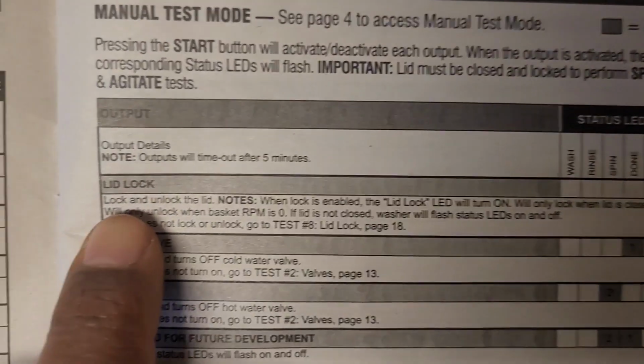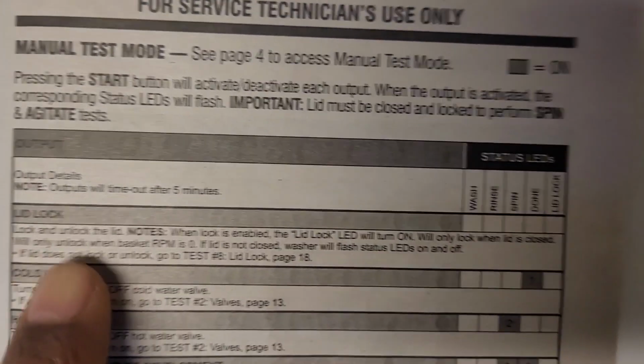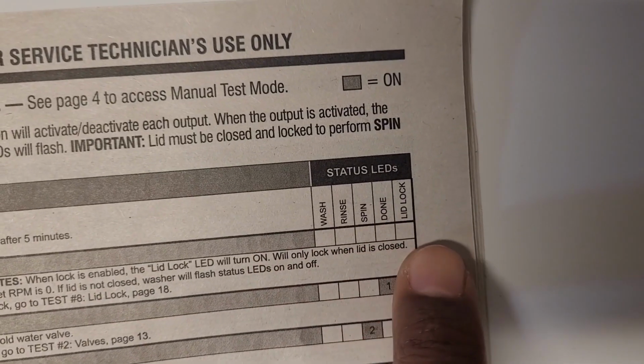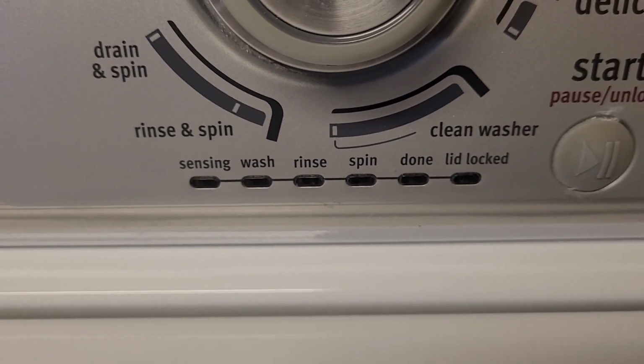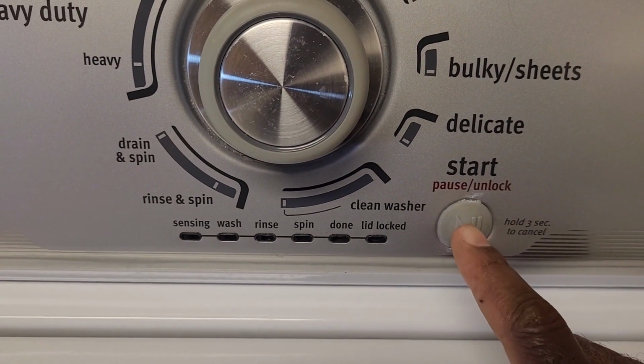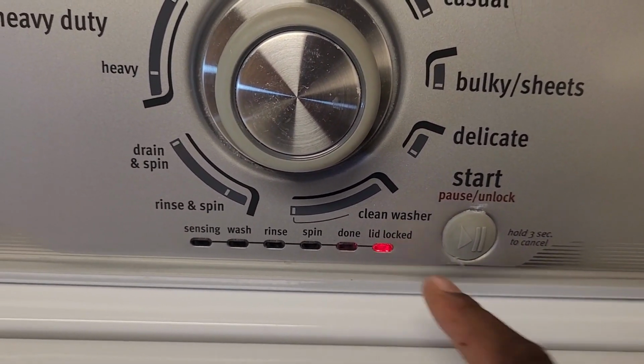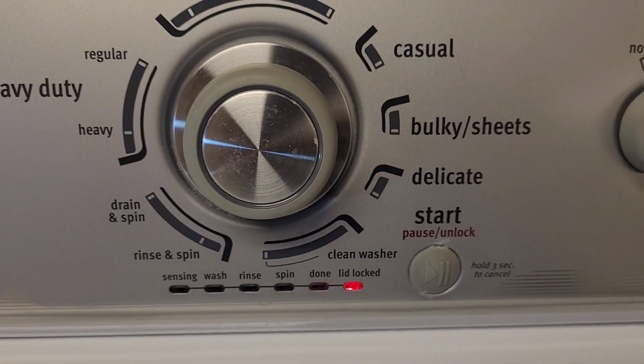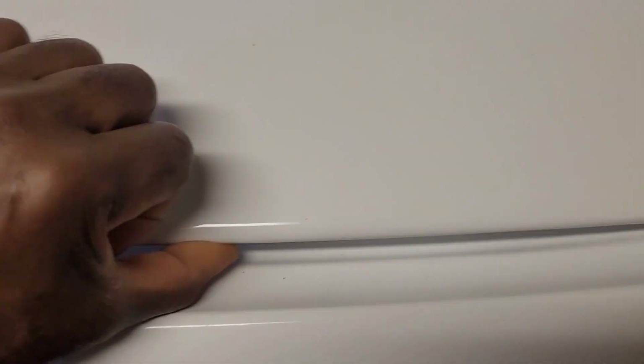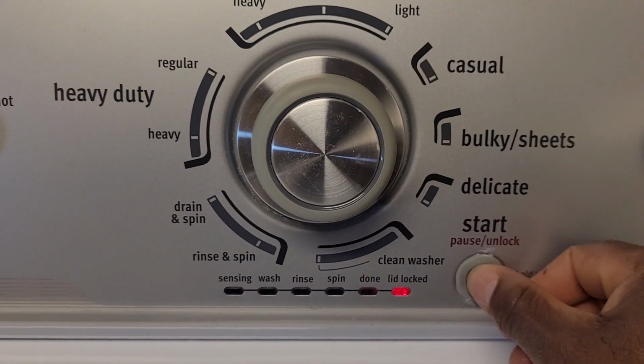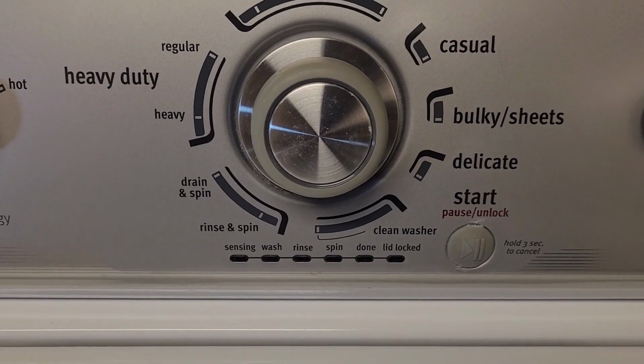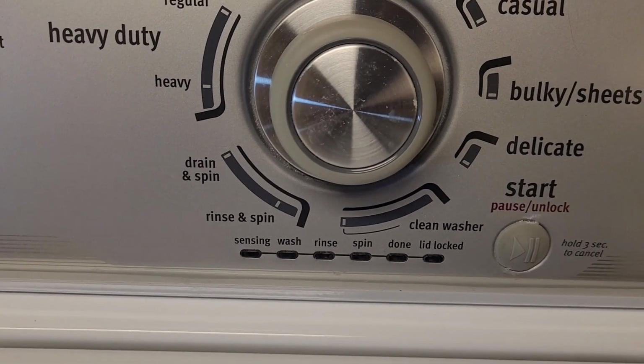For example, for the lid lock LED testing, you don't have to turn on any LED. Immediately after you get into the manual test mode, press this button to engage the test. See the light right there? It means the door is closed and it is locked. You can press this button one more time to disengage it, and now you can open the door. It means the door has no problems.